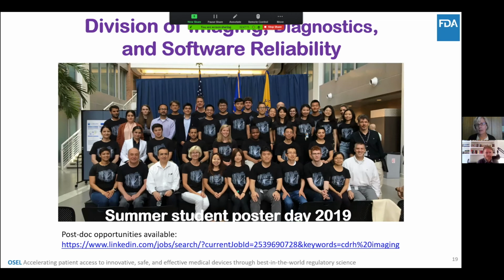We certainly are strong promoters of task-based evaluations. The challenge for CT denoising is that CT images, like all imaging modalities, exist with very generic claims around what kinds of images will be collected for what kinds of purposes. And so the approach that we've taken is to, first of all, look at the technical characteristics of the images, like I was just showing, impacts on those first level measures of imaging performance, like MTF, noise power spectrum, low contrast detectability.